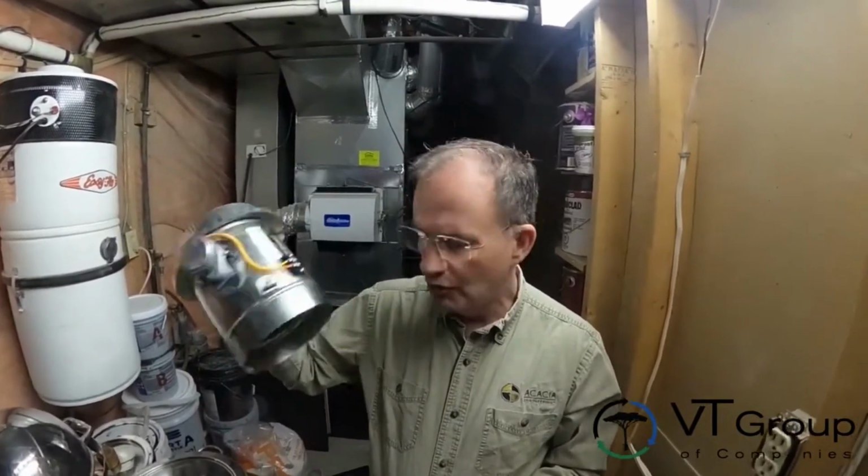There are other controls you can do with this. In the summer months, you could connect this to a temperature sensor for outside, so when it's cooler outside, you can get some free cooling. It's just a different way of wiring it. It works the same way: when the furnace fan is on but no heating is called, no fresh air is coming in. However, you have either a manual switch or a thermostat that says you want some cooling in the house, and you can allow fresh air in. That would be great for places like Calgary that get cooler in the evening, and you can take advantage of free cooling.